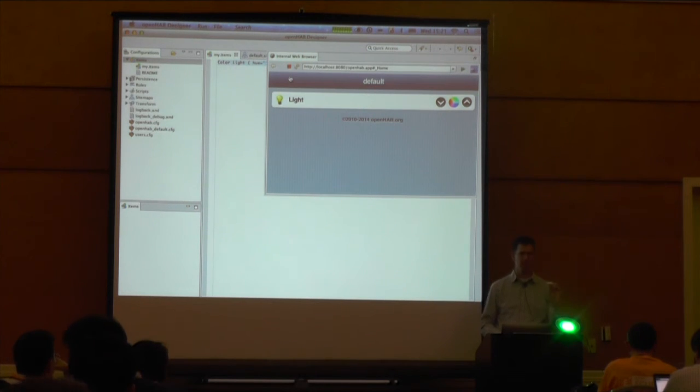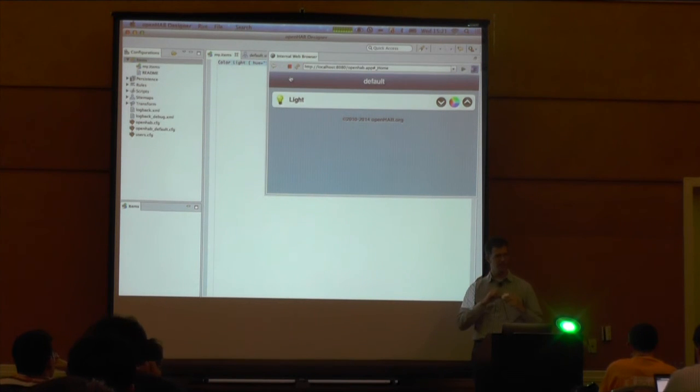It's a technology called EnOcean. So it's a radio protocol. And a special thing about it is they call that energy harvesting. So if I press here, you hear it clicking clearly. And this click, the energy that I put into the system by pressing is enough to send out the radio telegram. So thinking about Paul's security issues from before, the energy for that is definitely not enough to do a lot of encryption on it, okay? But still, for simple use cases where security doesn't matter too much, it's a really cool idea.